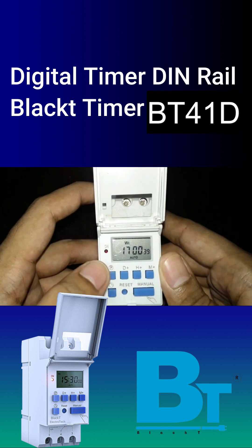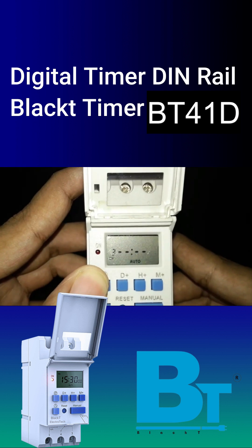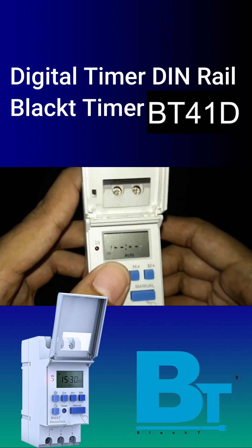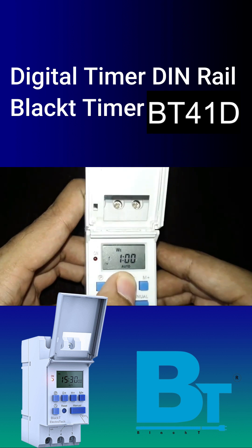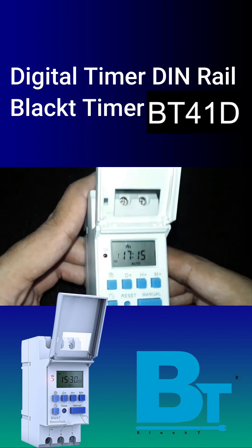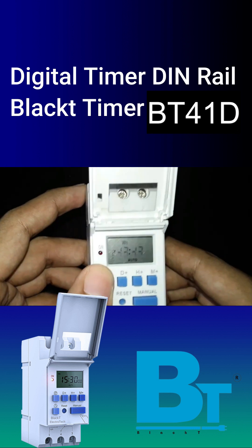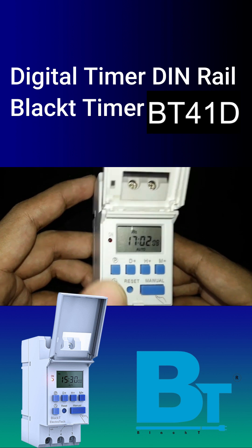After the time is set, let's see how to program. Press the P button once — you'll see 1 on, 1 off, 2 on, 2 off — and so on; you can do up to 20 on and off programs. For program 1, press P once, set the day, hour, and minute to turn the timer on, then set the day, hour, and minute to turn it off. For example, this timer will turn on at 5:15 PM and off at 5:17 PM. You can set your time programs in different settings. To exit, press the watch button.